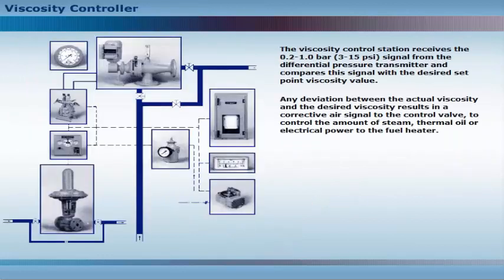The viscosity control station receives a 0.2 to 1.0 bar or 3 to 15 psi signal from the differential pressure transmitter and compares this signal with the desired set point viscosity value. Any deviation between the actual viscosity and the desired viscosity results in a corrective air signal to the control valve to control the amount of steam, thermal oil or electric power to the fuel heater.